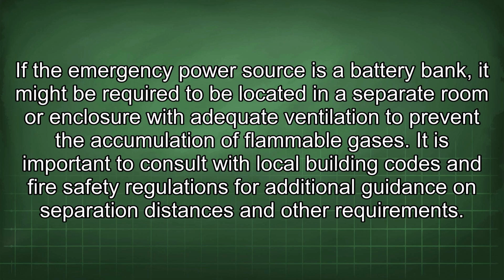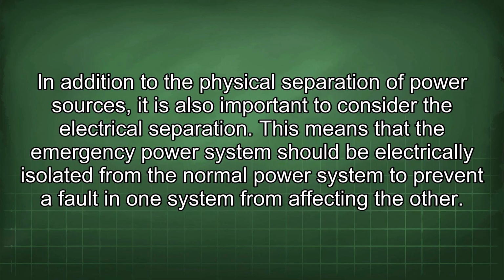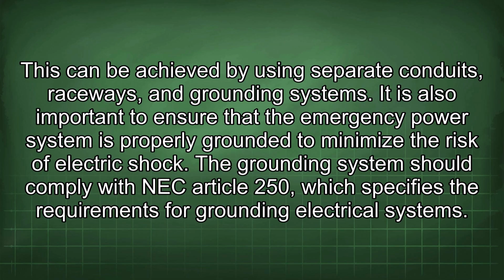other requirements. In addition to the physical separation of power sources, it is also important to consider the electrical separation. This means that the emergency power system should be electrically isolated from the normal power system to prevent a fault in one system from affecting the other. This can be achieved by using separate conduits, raceways, and grounding systems. It is also important to ensure that the emergency power system is properly grounded to minimize the risk of electric shock. The grounding system should comply with NEC Article 250, which specifies the requirements for grounding electrical systems.